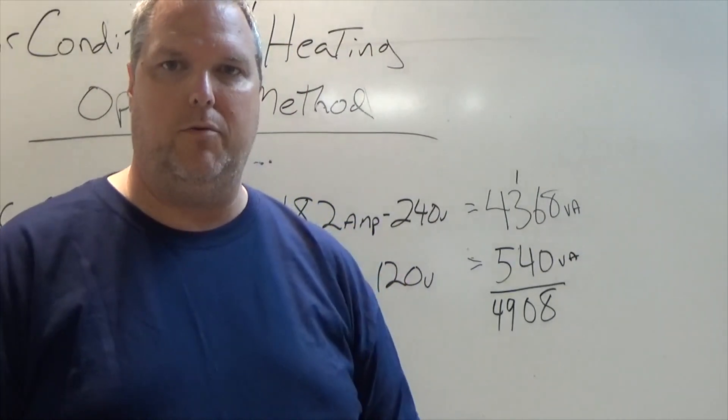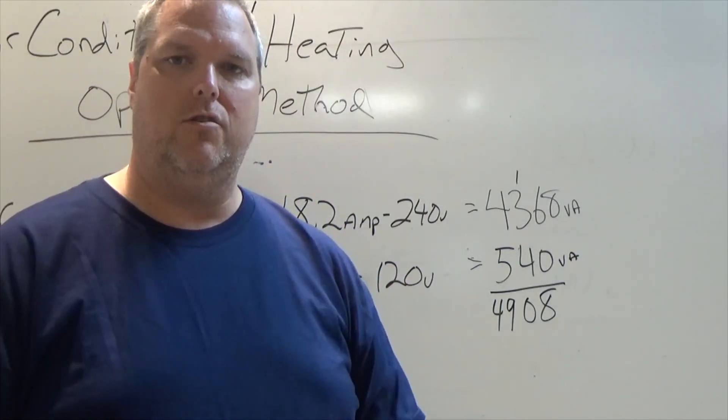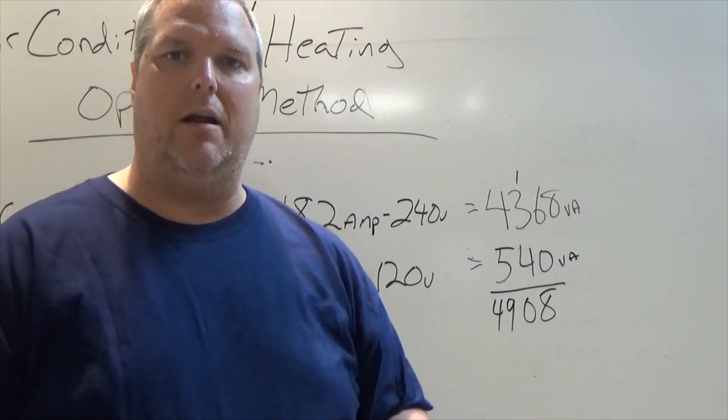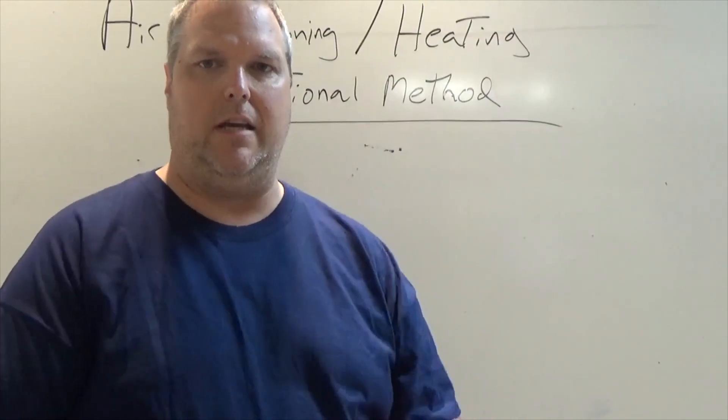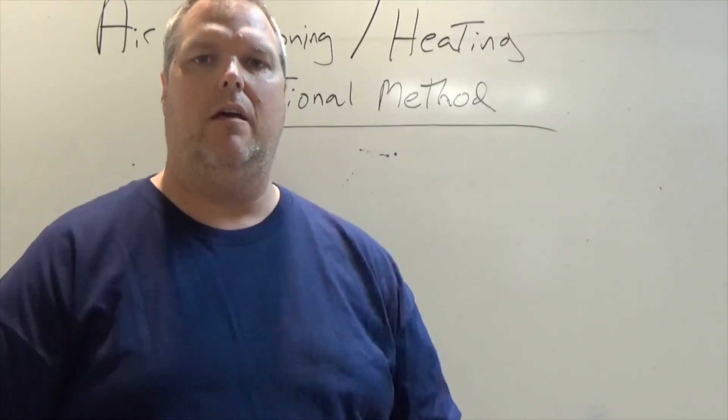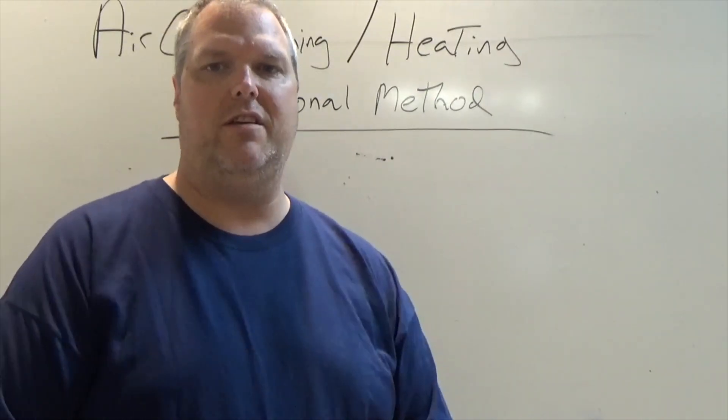So I add the two together and it gives me a VA for AC at 4908. 4908 is taken at 100% according to 220.82. So I'm going to take that, I'm going to put it aside and I'm going to compare the heating. So now that we've talked about AC, now let's talk about heat.